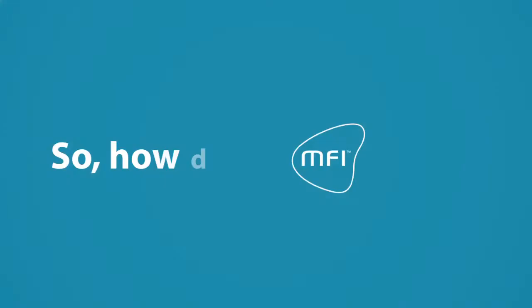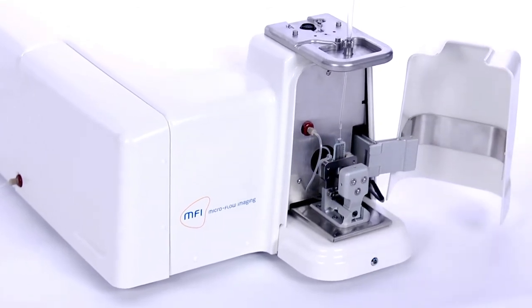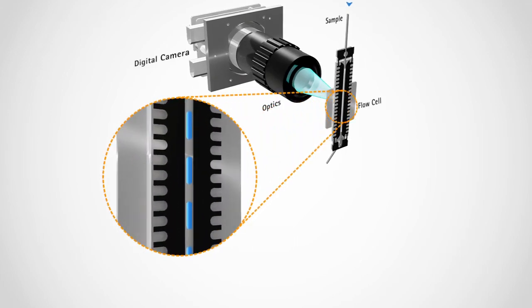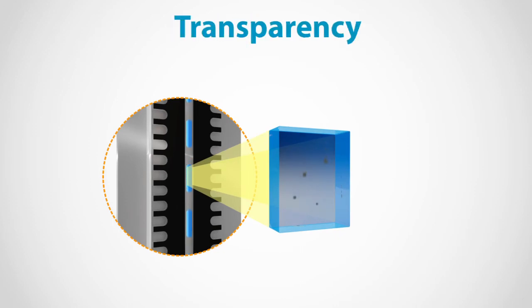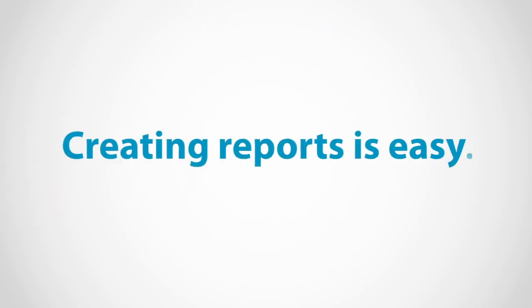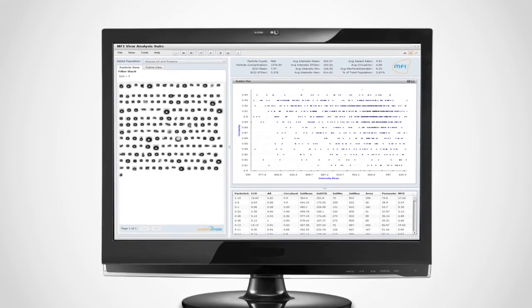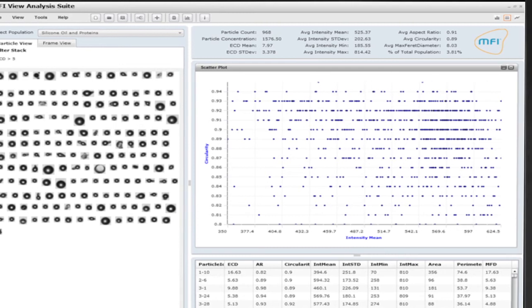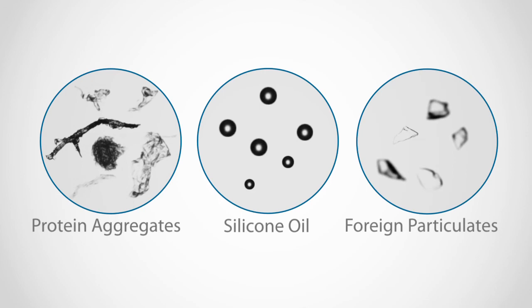How does MFI work? As the sample moves through the flow cell, MFI captures images and analyzes every particle. The system is precisely aligned for high sensitivity, and every particle is analyzed in real time for particle count, size, transparency, and morphology. Viewing data and creating reports is easy — simply set parameters to filter your data for size, intensity, and shape. You can differentiate particles such as protein aggregates, silicone oil droplets, air bubbles, and other foreign particulates.